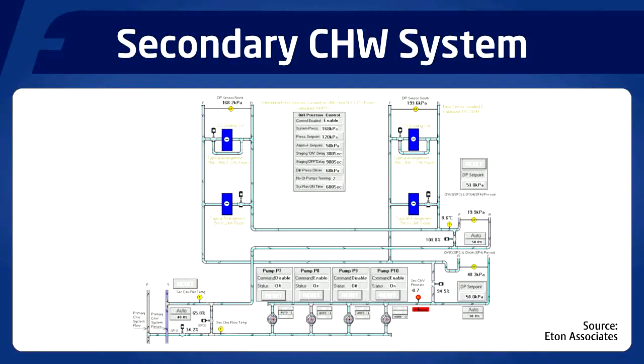We're concerned with level 6, where we installed the pressure independent control valve on the south riser air handling unit and monitored performance, whilst we also monitored performance of the conventional 2-port modulating valve on level 6 air handling unit on the north riser. Of course, there could be some different occupancy loads on floor 6 and certainly different solar gains due to the orientation of the building. Therefore, after 2 weeks, we exchanged places of the two valves and recorded data for a further 2 weeks in order that we could average out the month's data and negate some of the variables mentioned.